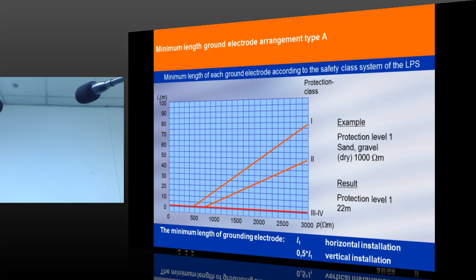For example, LP lightning protection level 1, level 2, level 3 and 4, and on the x-axis you can see the soil resistivity, and this is the length of the electrode. Imagine you are going to have a building with level 3, class 3 protection or class 4 protection. What is recommended in the standard is about 5 meter or maybe 6 meter long conductor in contact with soil is enough to dissipate the current. And if you go for higher protection, then you need to have a longer earth electrode. This is only for type A.